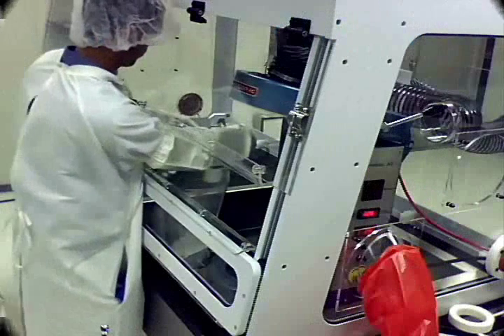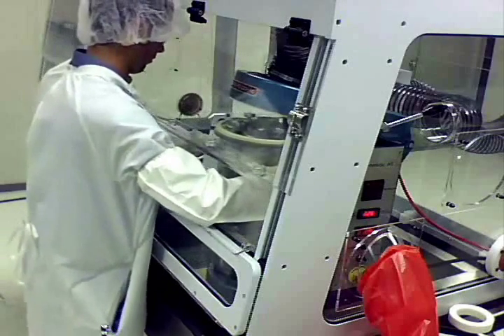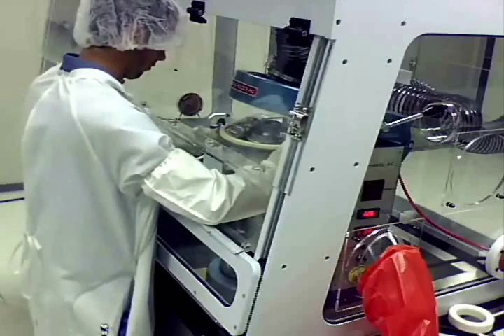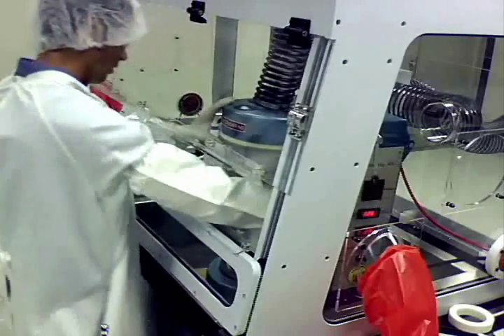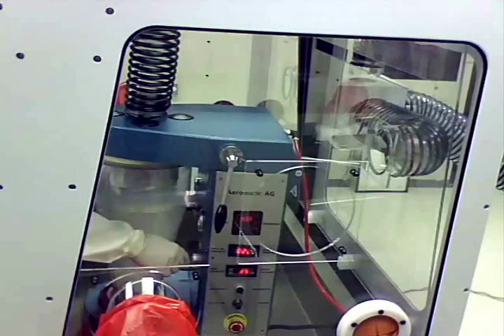The first process tested was a fluid bed dryer operation. The fluid bed dryer was placed on the removable cart base and rolled into the cutout of the enclosure. A pre-weighed sample of 500 grams of lactose was placed in the fluid bed dryer container. The fluid bed dryer was turned on and the flow rate of heated air was adjusted so that the powder in the container was allowed to rise halfway up the container. The operator continuously adjusted the flow rate to obtain this powder level.